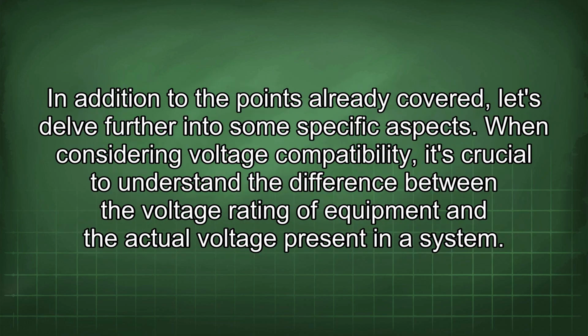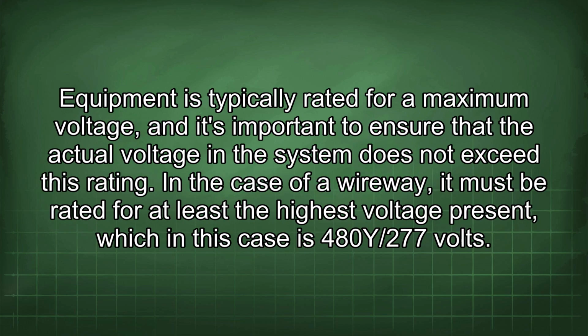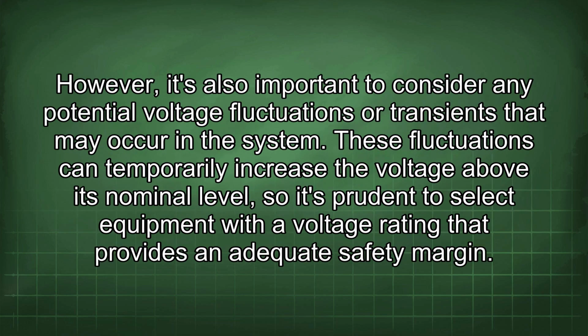In addition to the points already covered, let's delve further into some specific aspects. When considering voltage compatibility, it's crucial to understand the difference between the voltage rating of equipment and the actual voltage present in a system. Equipment is typically rated for a maximum voltage, and it's important to ensure that the actual voltage in the system does not exceed this rating. In the case of a wireway, it must be rated for at least the highest voltage present, which in this case is 480Y/277 volts. However, it's also important to consider any potential voltage fluctuations or transients that may occur in the system. These fluctuations can temporarily increase the voltage above its nominal level, so it's prudent to select equipment with a voltage rating that provides an adequate safety margin.